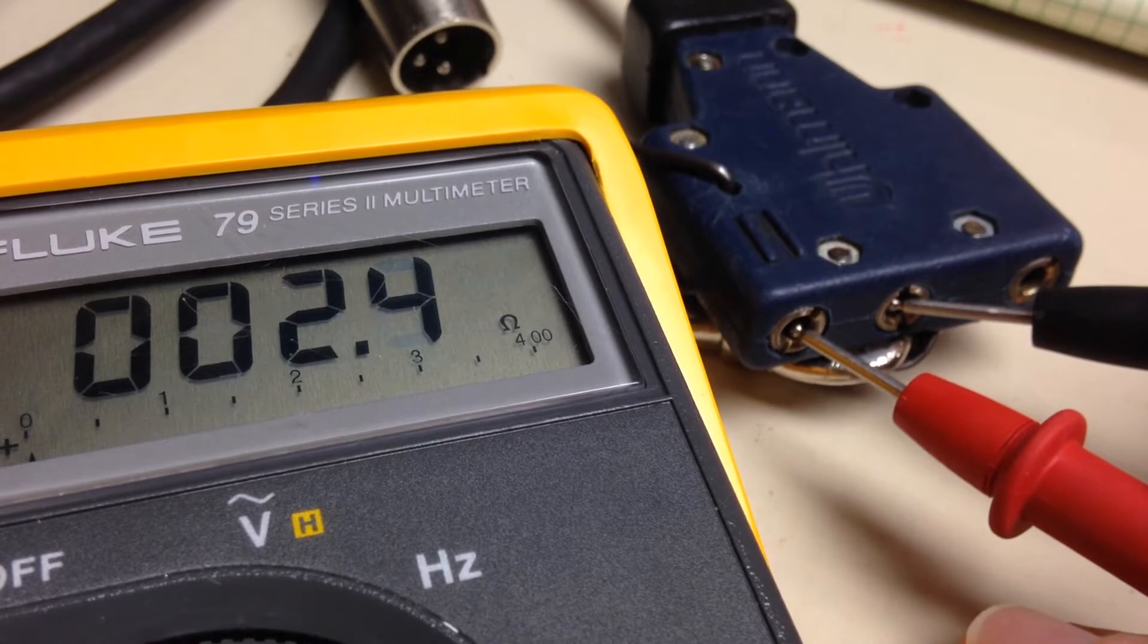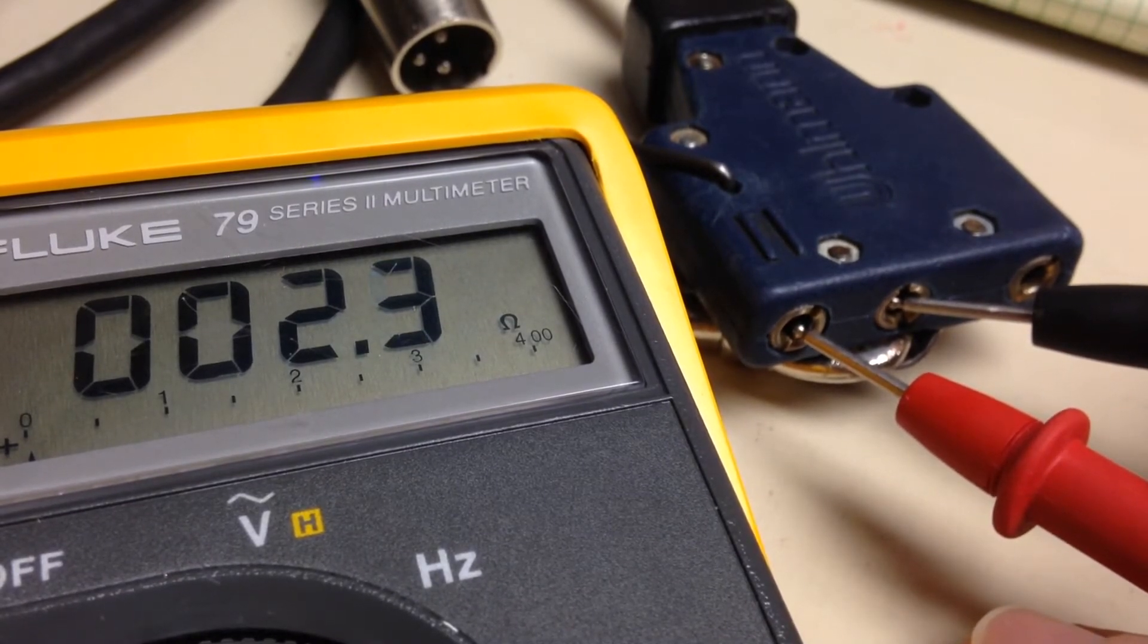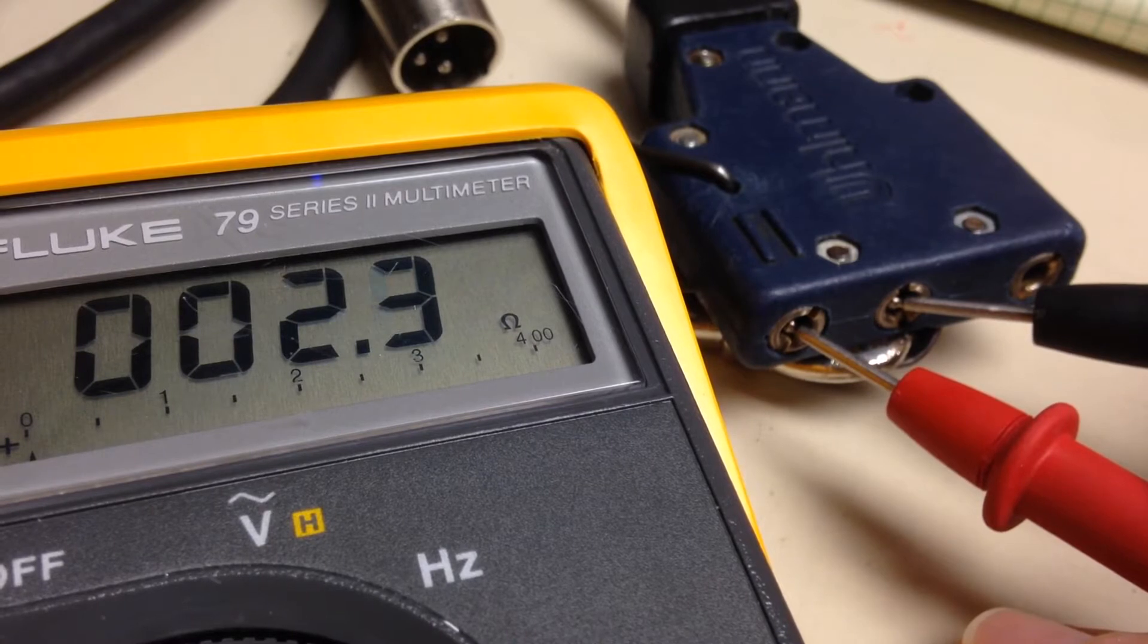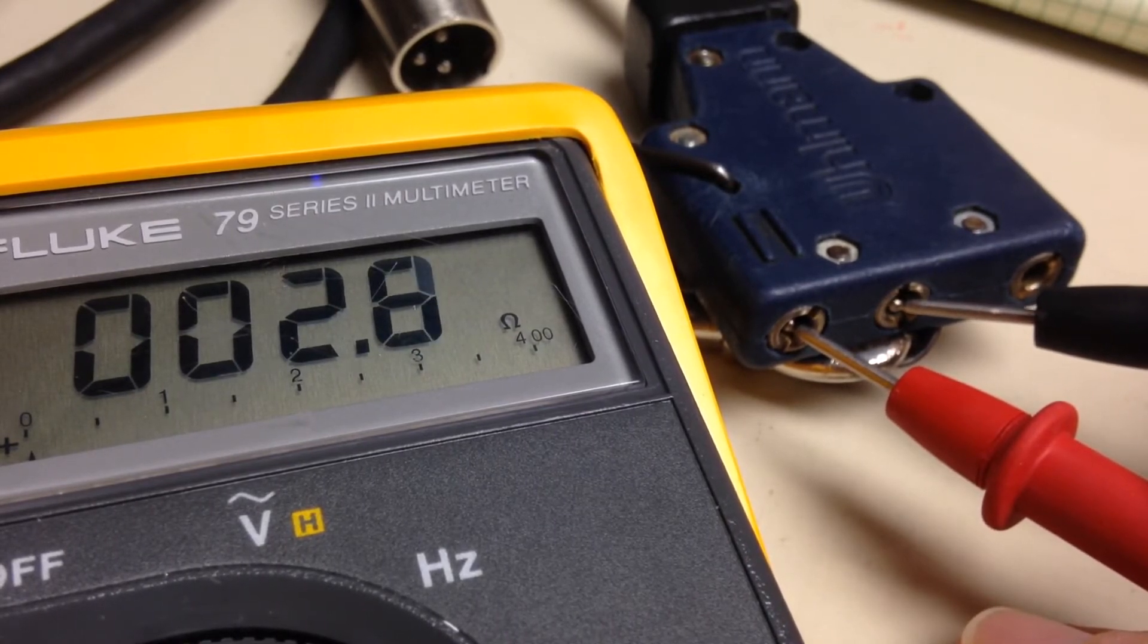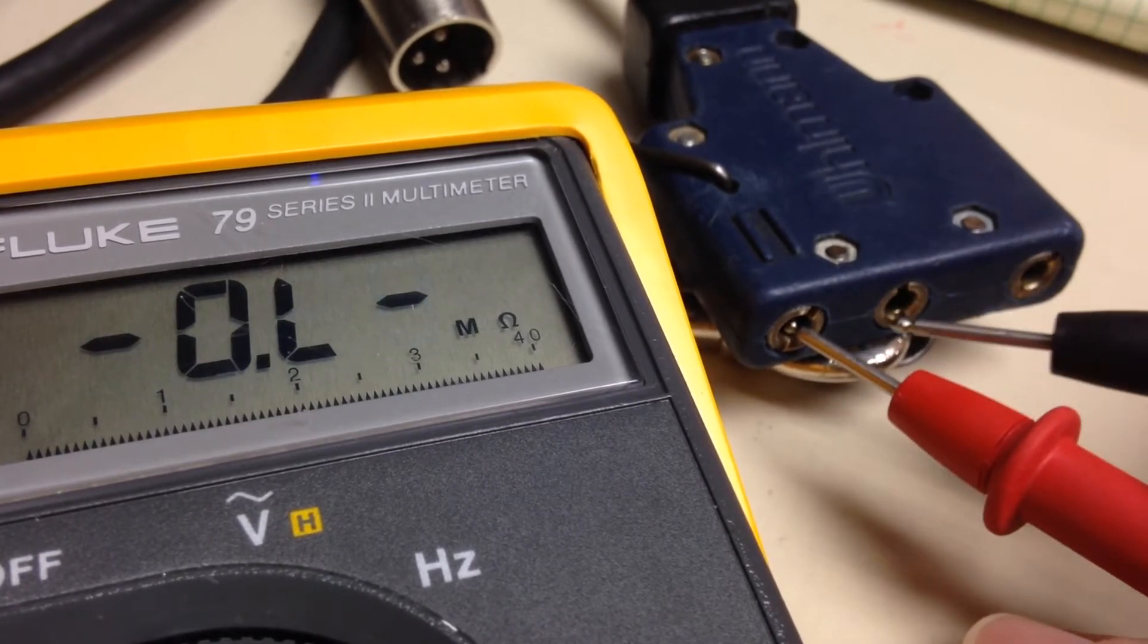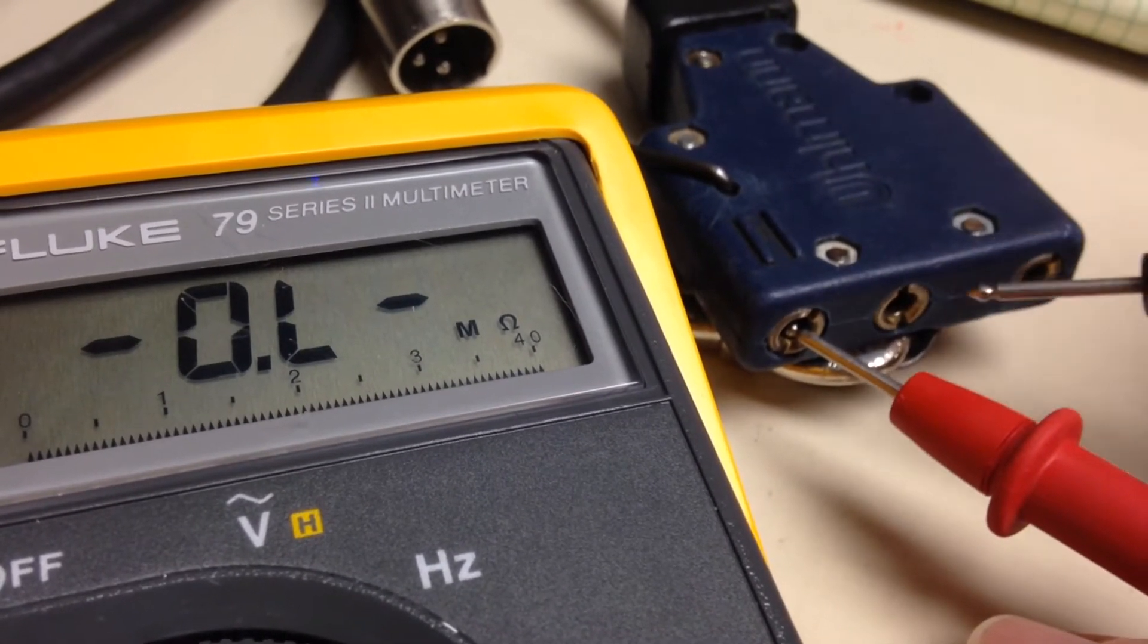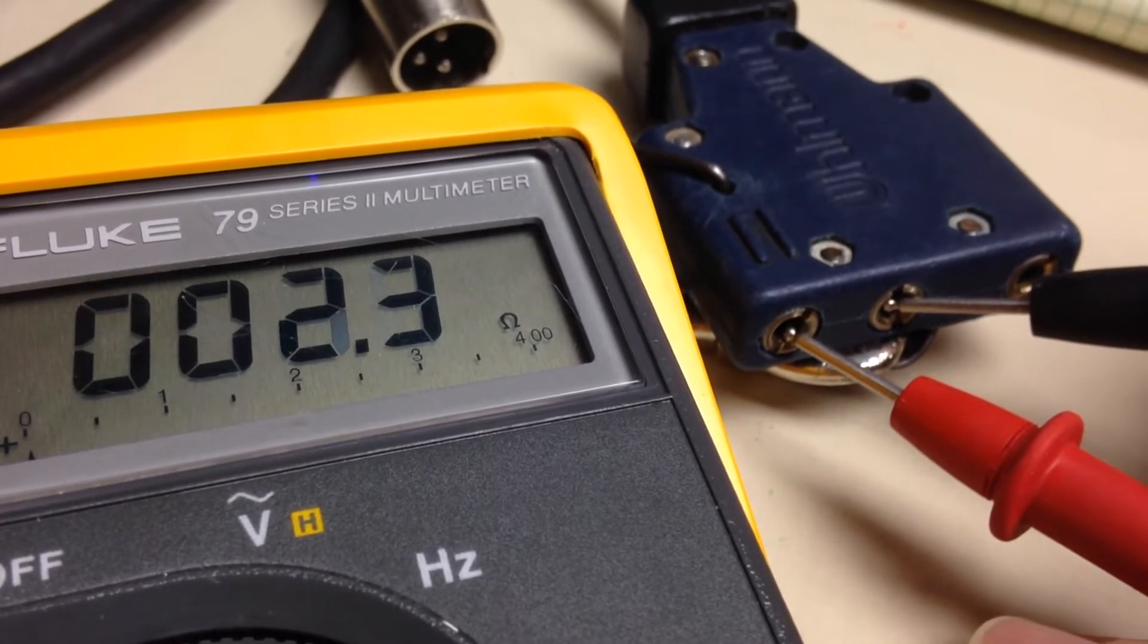One way you could diagnose this is you could put some current through the line and figure out where it's getting hot. You could end up possibly burning your short out and it could show up later. So we're going to use a more scientific method of diagnosing this. We could run current through the line, not enough to heat it up, and maybe look at the potential drop and use that to try to figure out approximately linearly where the short is down the line. But there's a better way to do it using the TDR method.